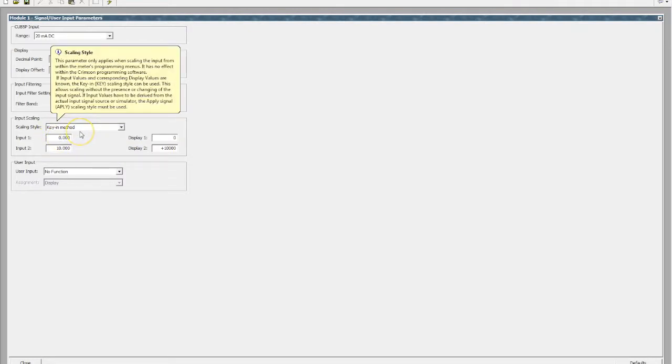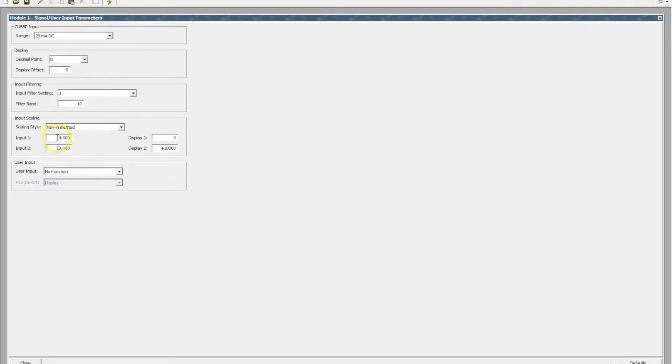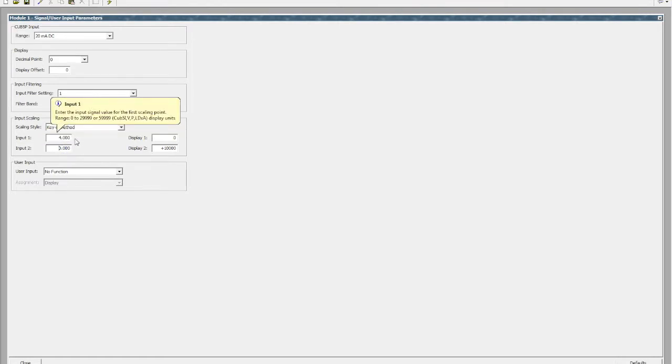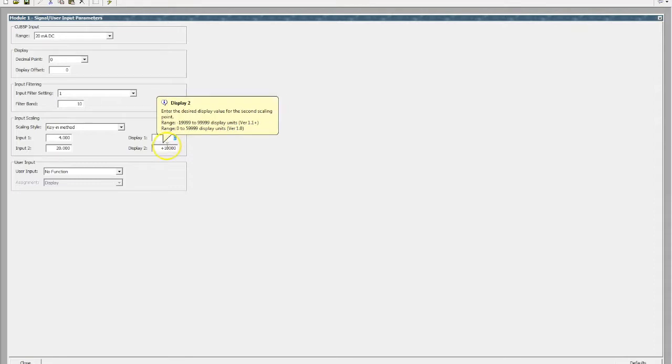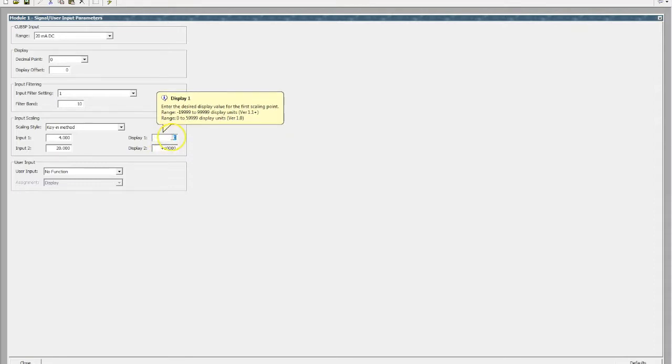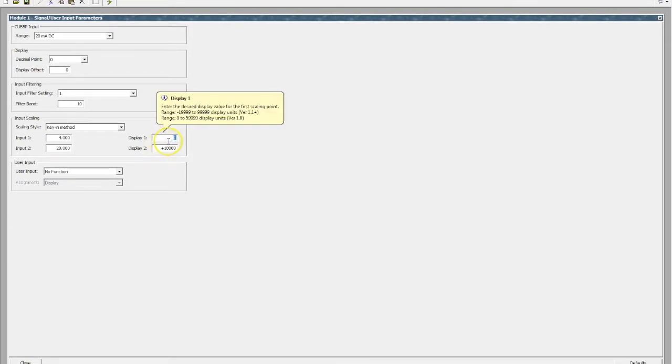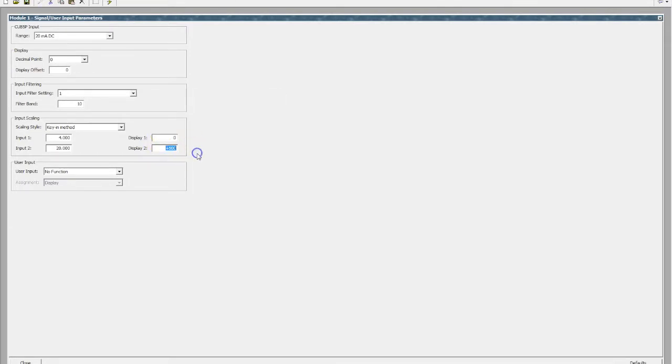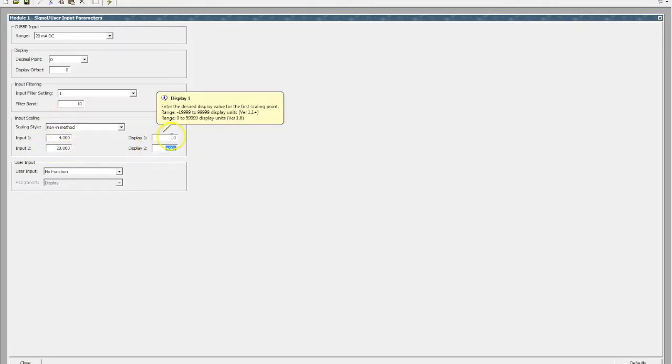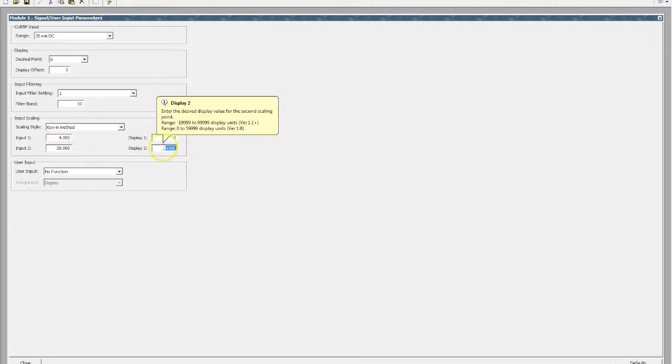So if our input is a 4 to 20 milliamp, we'll update our 4 to 20, then we nominate what that should display on the screen, especially where it's simple linear applications. We can choose, let's say it's a level of a water tank and we've got 0 to 500 liters. That's it. So now as we get a 4 to 20 milliamp signal, we'll get a 0 to 500 value displayed on our unit.